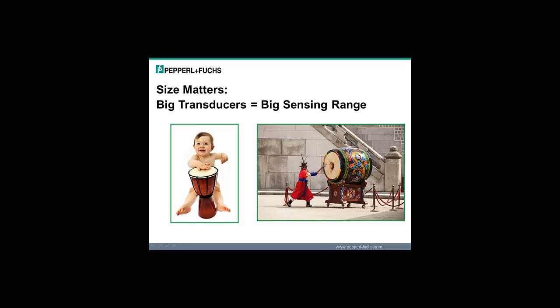So we've discussed the UB300 and the UB1000, the UB800. So we're talking about all these different sensing ranges that are available. But size does matter for an ultrasonic transducer. So the bigger the drum, the more power, the further you can see a target. And likewise, the smaller is going to be a smaller beam angle, higher frequency, and you've got to be a little bit closer in order to see the target.